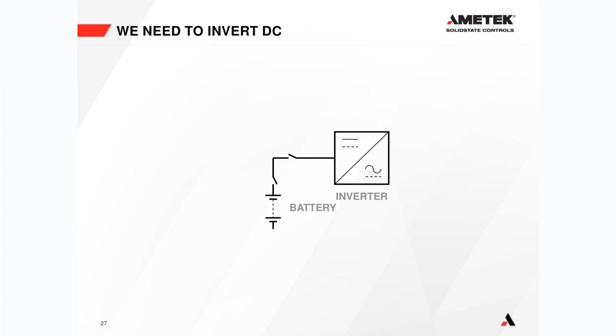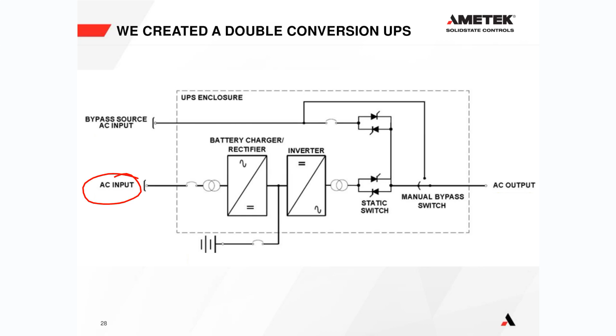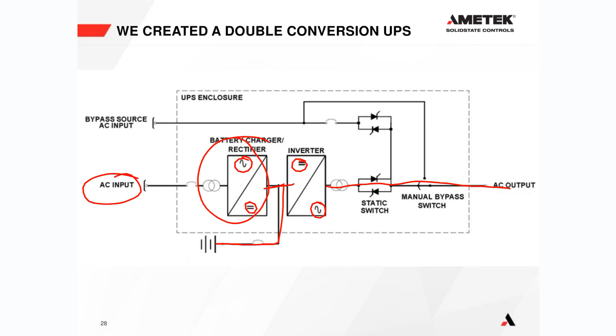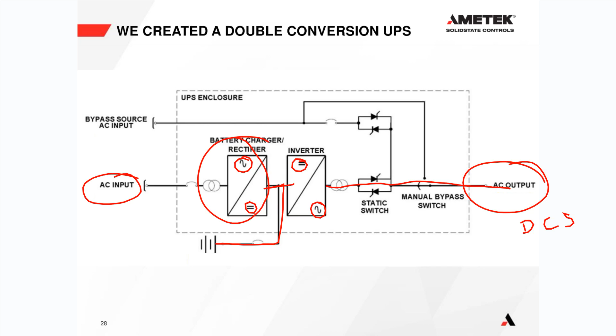This is the single line diagram for an AMETEK solid state controls double conversion UPS. We have our AC input going in here. Our battery charger rectifier converts that AC into DC and keeps the battery charged. Then that DC goes into our inverter, which gets changed back into AC, which goes out through a static switch - which I'm not going to explain on today's webinar - and then out to our AC output, which is all your load circuits, whatever critical equipment you've got connected that can't lose power.